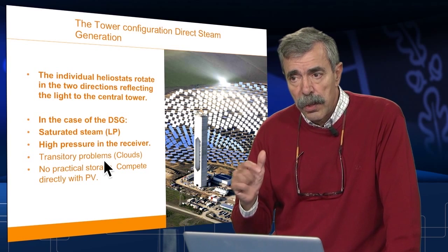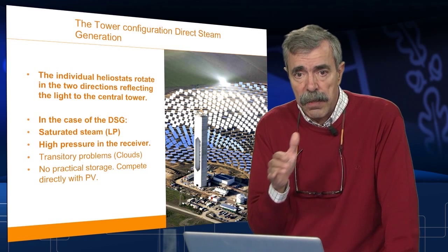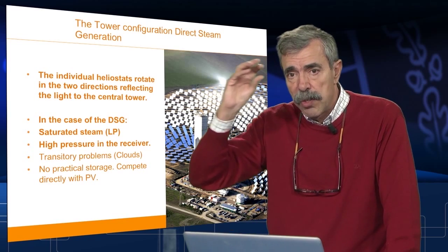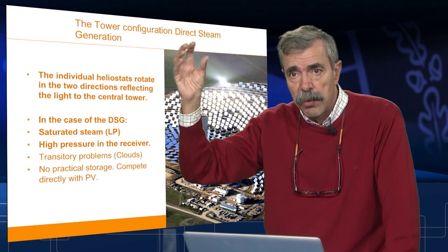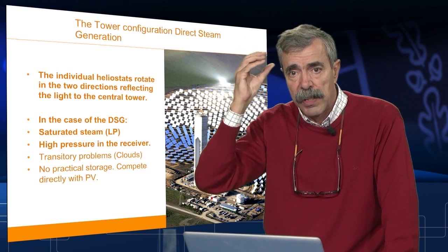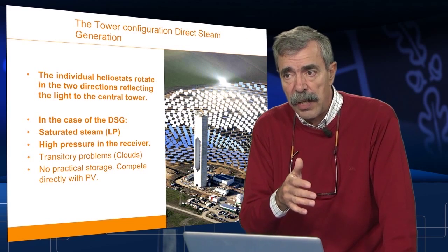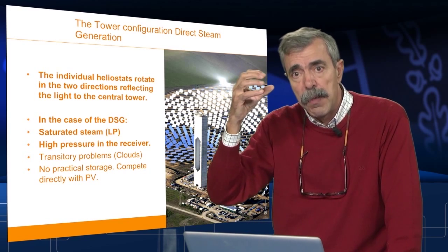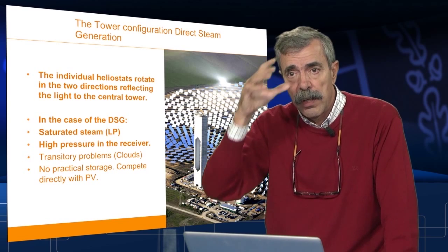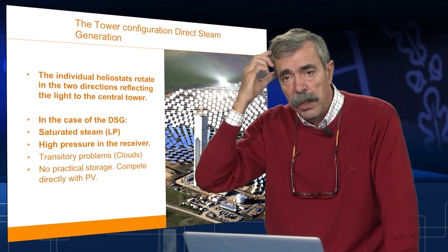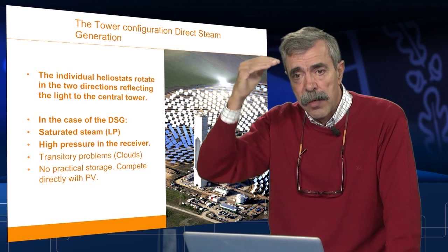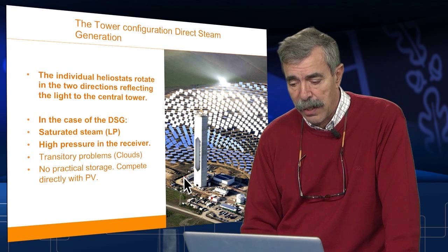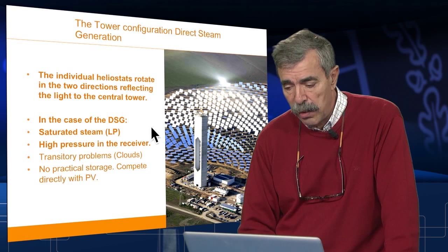Nothing to say about when this is happening not just at the expected moments, but just because there is a cloud moving on the horizon and you don't know exactly if it is going to affect you or not. So in the middle of the day, the stress that can be produced just because suddenly a cloud removes the energy and reduces the temperature of the receiver has a relevant effect on the durability of the receiver.